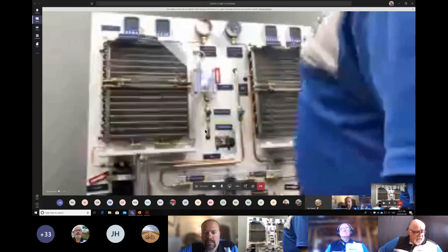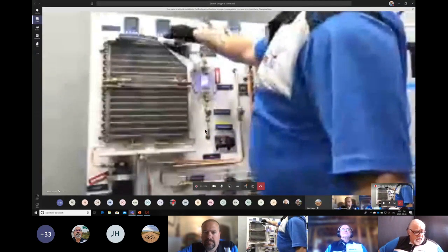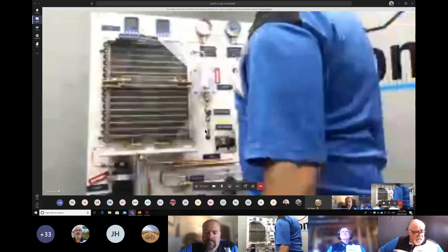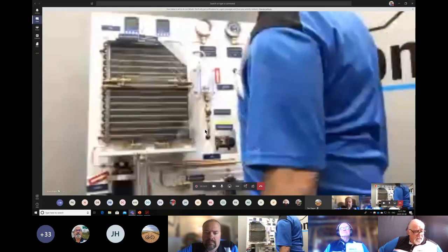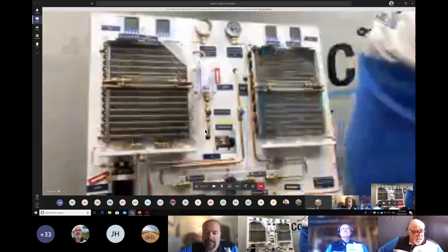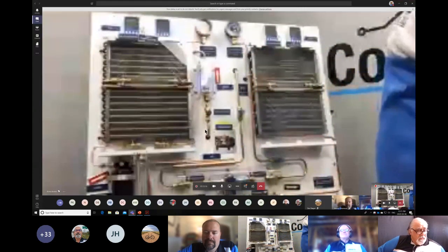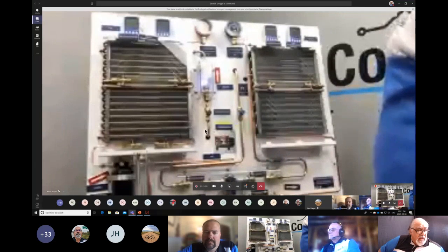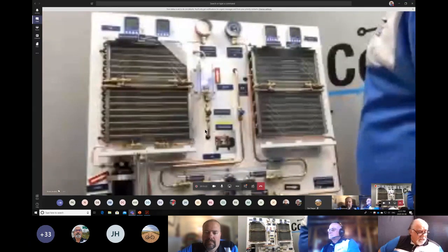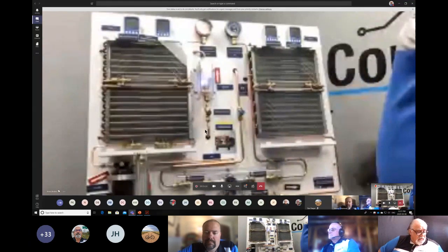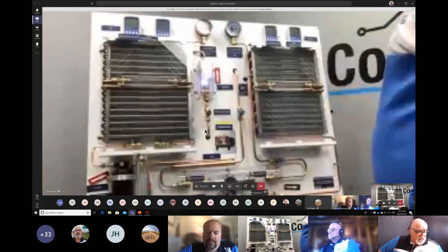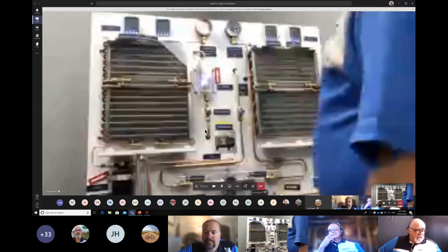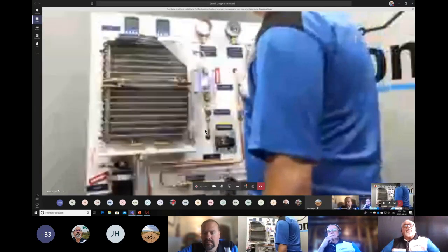Okay, so the condenser out, I have 106.3 degrees, and I am at 155 psi. So again, back to our chart, 155 psi goes to 114 degrees Fahrenheit. So we got 114 minus 106. So again, we're in that 8 degrees of subcooling.